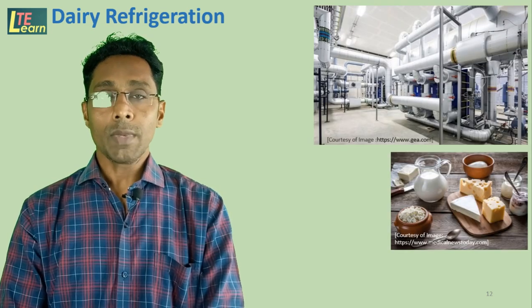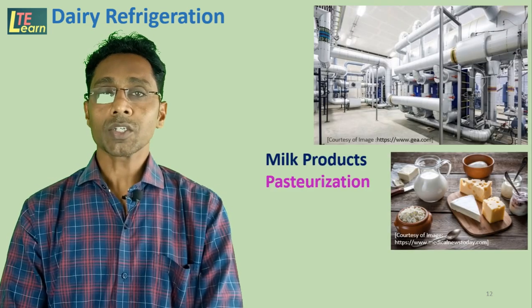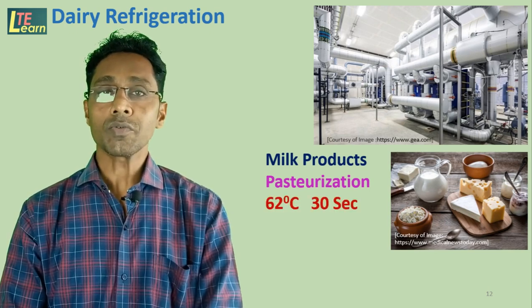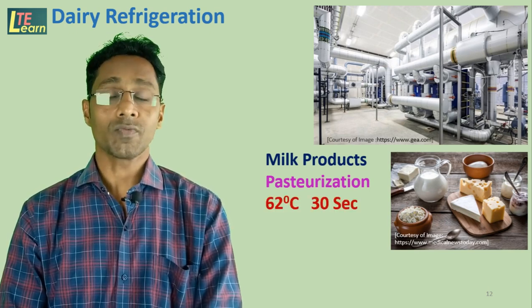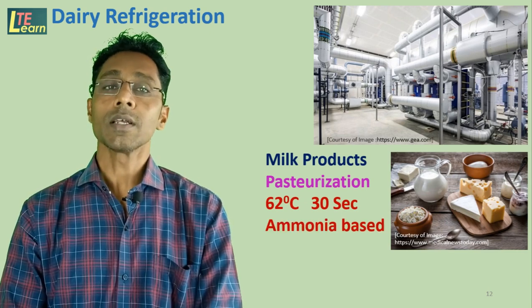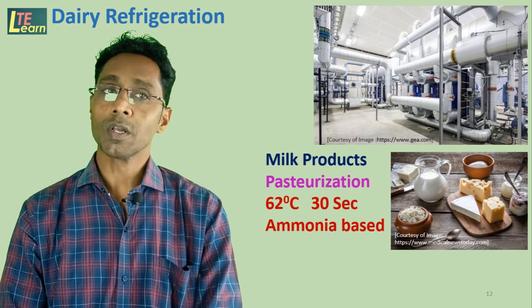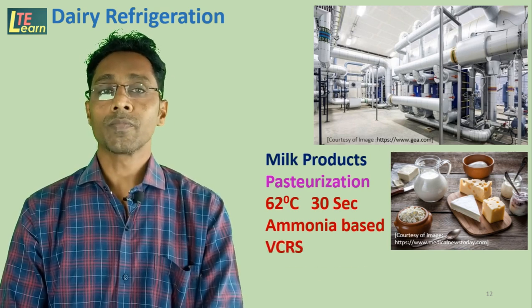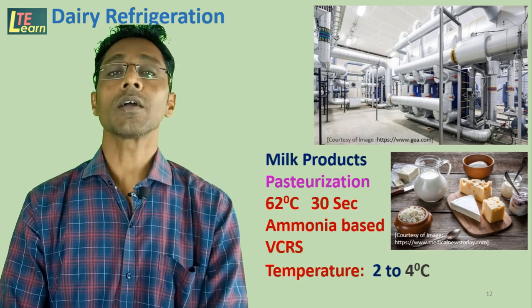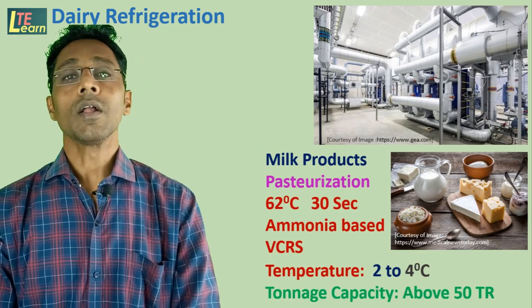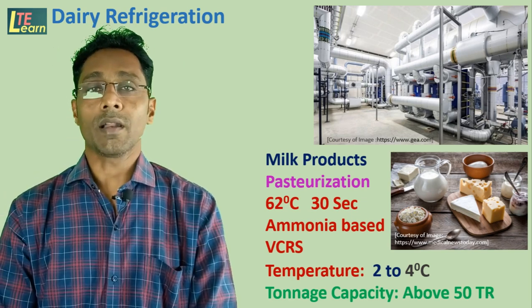Dairy refrigeration: In the case of milk products, pasteurization of milk is performed. Milk is heated to 62 degrees Celsius, held for 30 seconds, then cooled to 4 degrees Celsius and stored. An ammonia-based VCRS is used, with a temperature range of 2 to 4 degrees Celsius. Tonnage capacity for dairy refrigeration is above 50 TR.